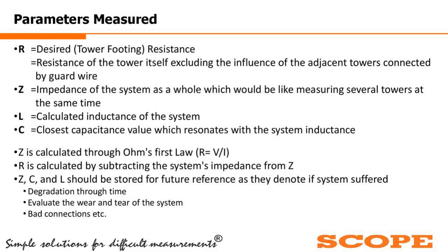Calculated inductance of the system is also virtually calculated, and the closest capacitance value which resonates with the system inductance is found. So in this instrument, something like an RLC bridge balancing is taking place at high frequency, a quick measurement, and then we get the value of R. The value of R is once again dependent on the fall-of-potential method, at which distance you are measuring. So I need to keep the distance as required, and then we will get all the things.